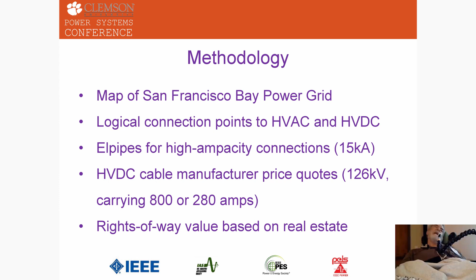In my map, I had two different kinds of connections, cables at two different ampacities, 285 and 800 amps, and L-pipes. L-pipes are my invention that was aimed at the supergrid. I did most of my work modeling 800 kV L-pipes, whereas this is a lower voltage, although it's still in the HVDC range, 126 kV, and that implies pretty high ampacity. For this model, 15,000 amps is what I modeled them for.